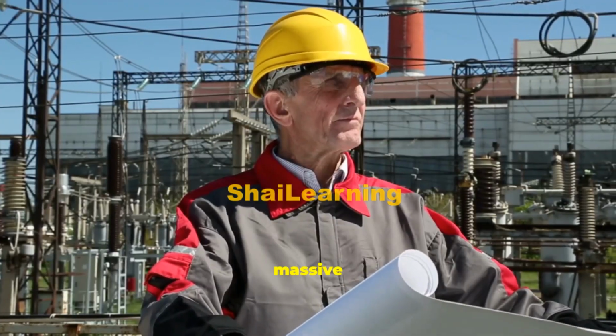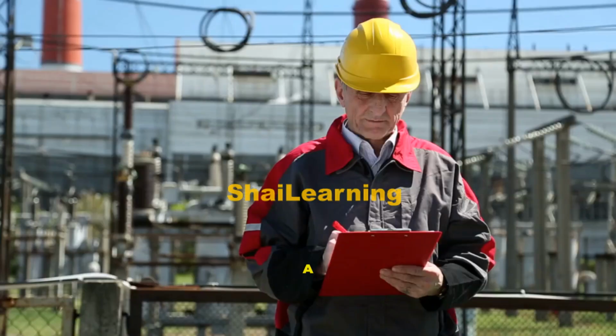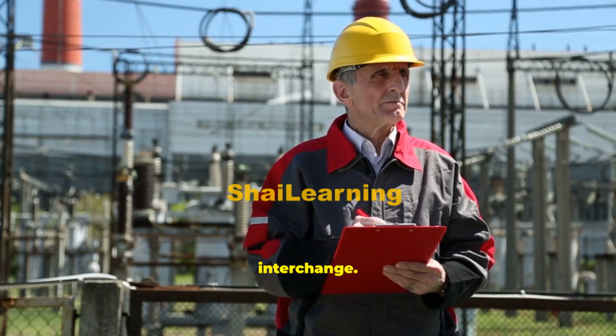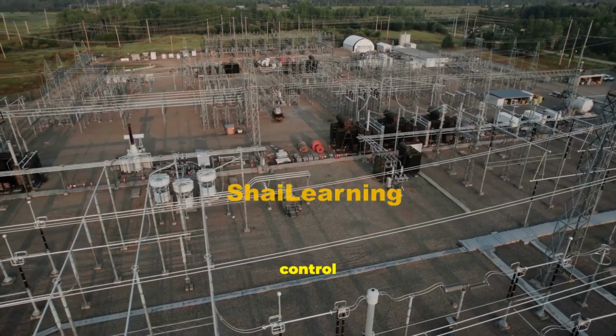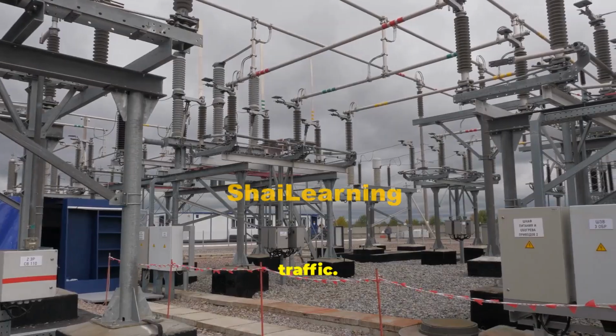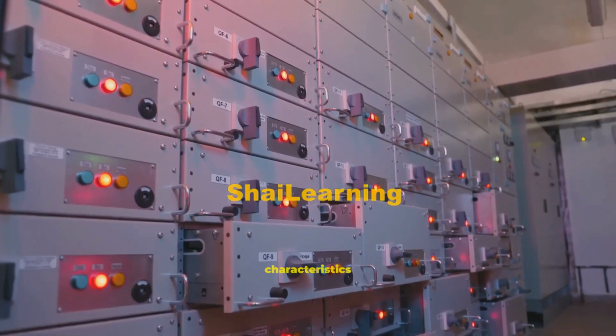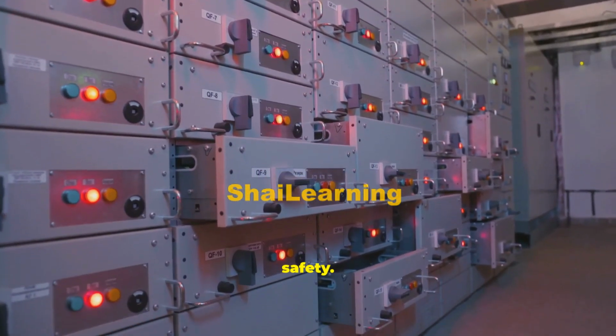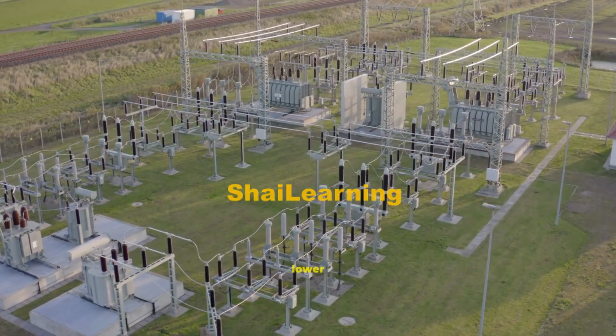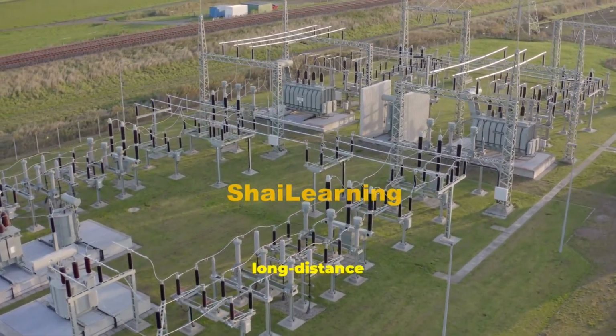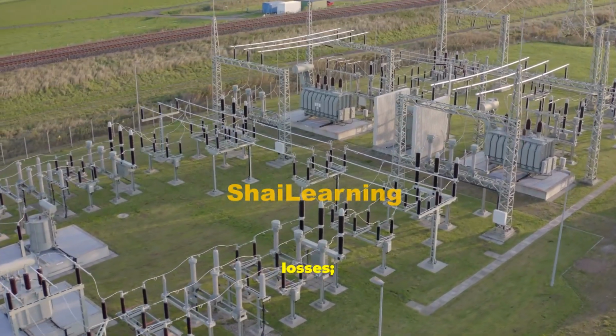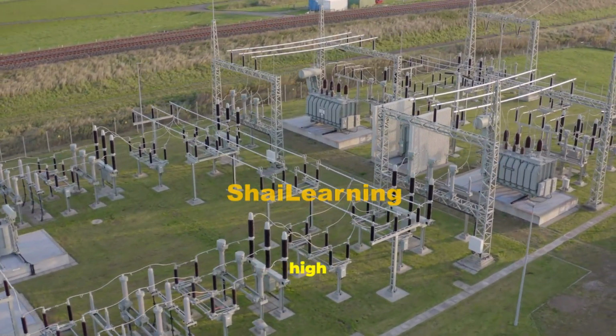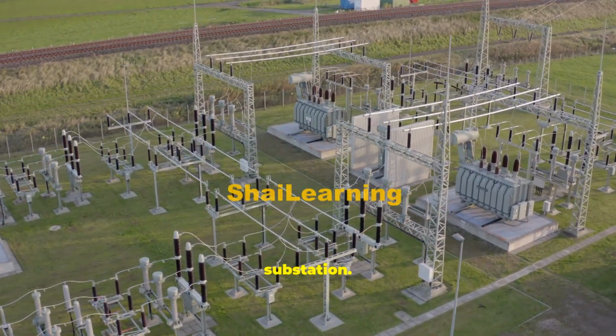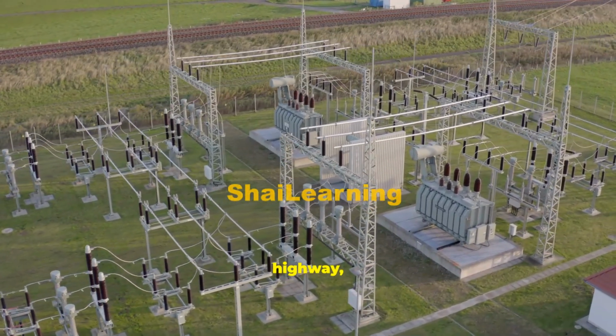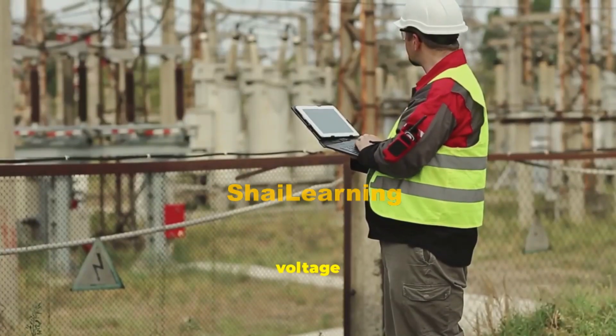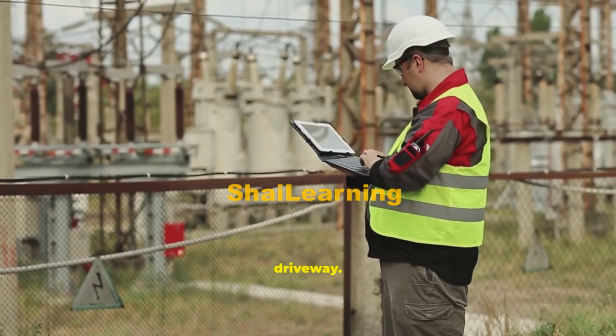Imagine the power grid as a massive network of highways. A substation acts like a major highway interchange. A substation acts like a traffic control center. It directs electrical traffic. It changes electricity's characteristics and ensures safety. Electricity is generally produced at a lower voltage, which is not suitable for long-distance transmission due to electrical losses. As such, the voltage is converted to high voltage at the generator substation. Now the high voltage hits the highway, that is the transmission line, but that high voltage is too dangerous for local streets or your driveway.